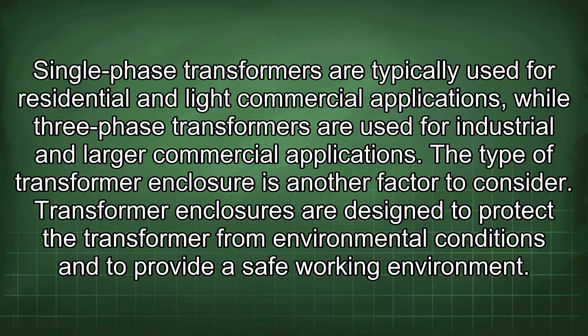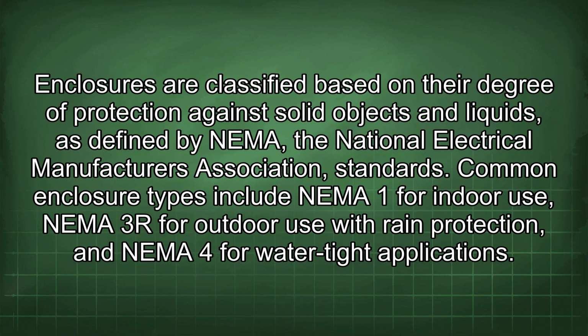Single-phase transformers are typically used for residential and light commercial applications, while three-phase transformers are used for industrial and larger commercial applications. The type of transformer enclosure is another factor to consider. Transformer enclosures are designed to protect the transformer from environmental conditions and to provide a safe working environment. Enclosures are classified based on their degree of protection against solid objects and liquids, as defined by NEMA, the National Electrical Manufacturers Association, standards. Common enclosure types include NEMA 1 for indoor use, NEMA 3R for outdoor use with rain protection, and NEMA 4 for watertight applications.